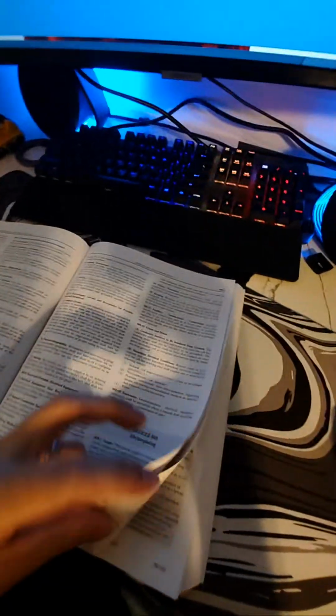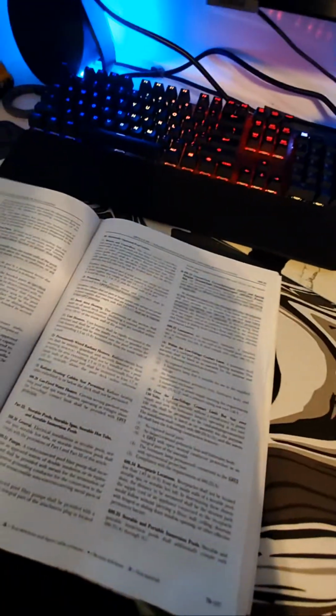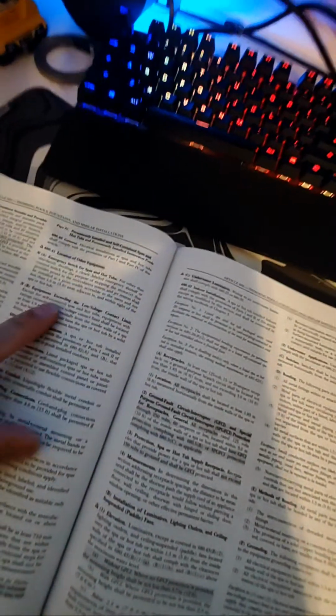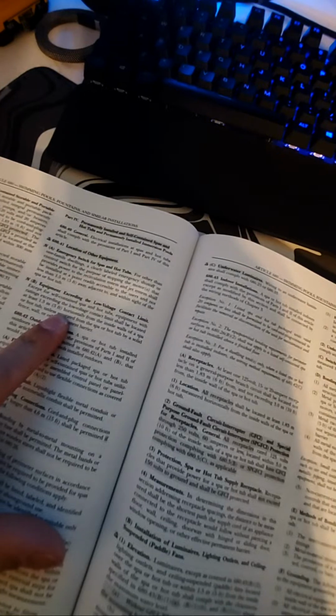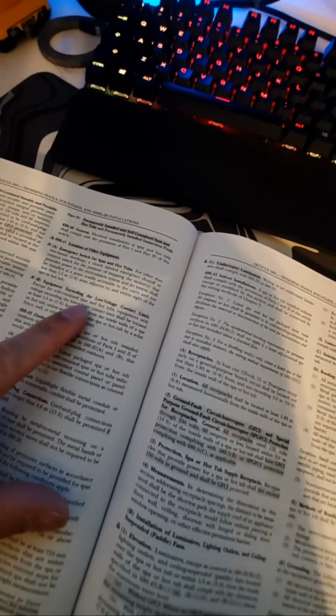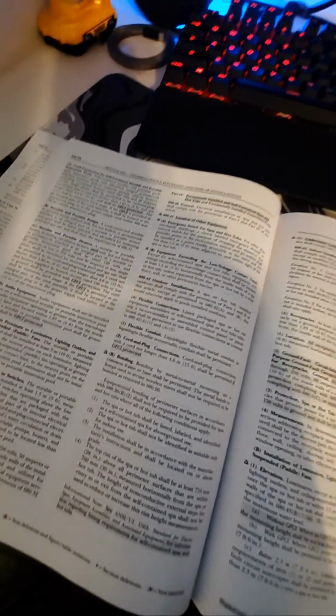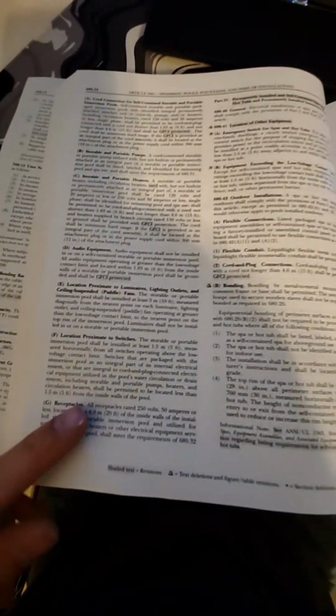There's natural, artificially made bodies of water. We're looking for permanent, storable pools that have different things. Swimming pools, fountains, or similar installations. They should have a hot tub part in here somewhere. Looks like there's a spa there. Spas and hot tubs. That's going to be, there is some requirements for some spacing there, but we're looking for receptacles. So we're going to look for receptacles. Here we go. Receptacles, all receptacles 50 amps or less, located within 20 feet.